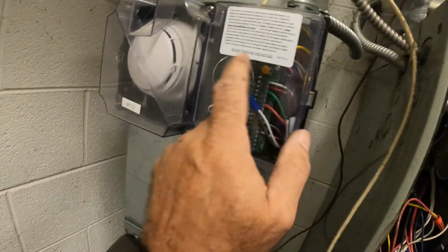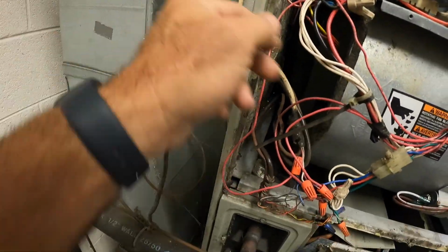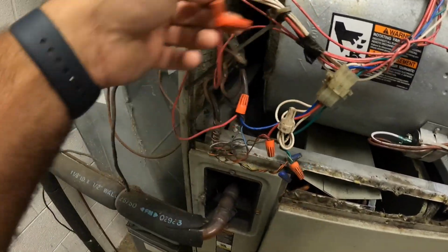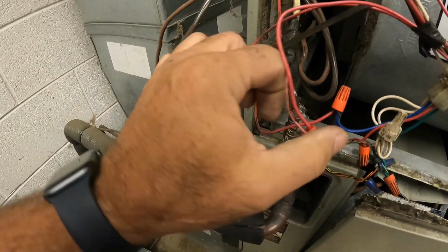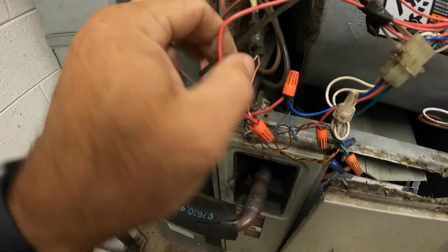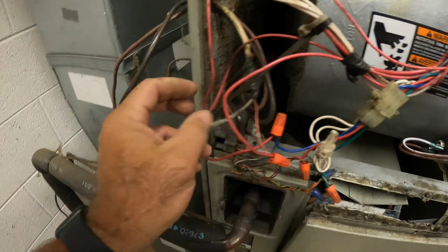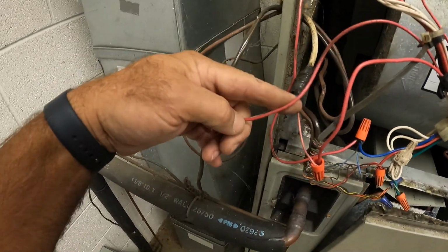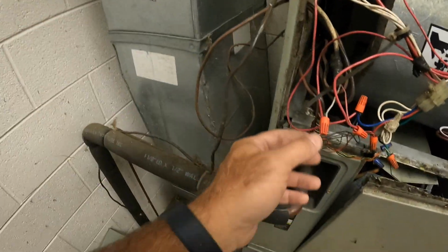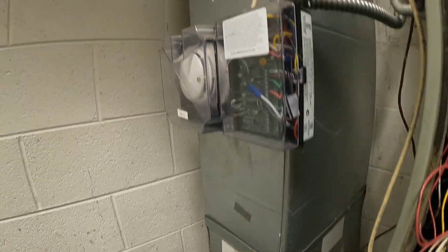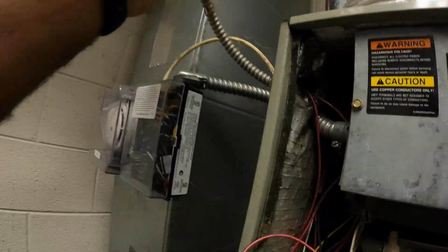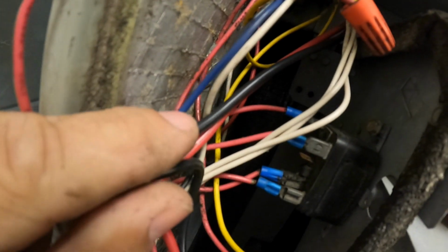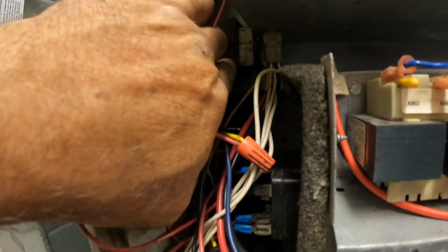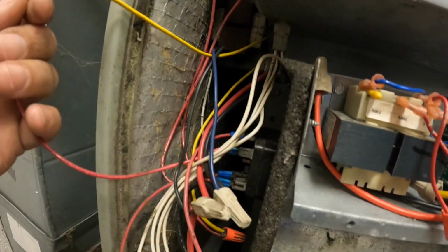Again, this little white wire, it's probably just a set of dry contacts here, but you can see it comes in here, has two wires, red and white, and all it's doing is breaking the red wire on the air handler, which will kill the blower and everything else if there's a fire. However, this damper here, it's got its own little relay in here and its own transformer, because this is the unit transformer and that guy back there is for the damper apparently.